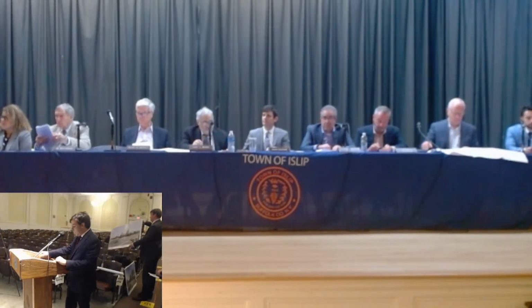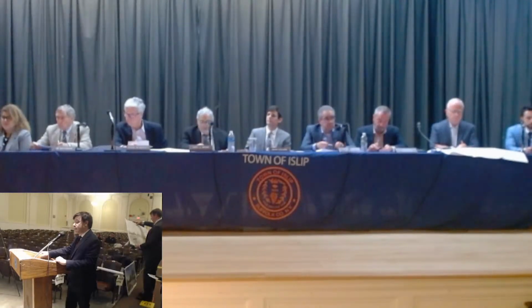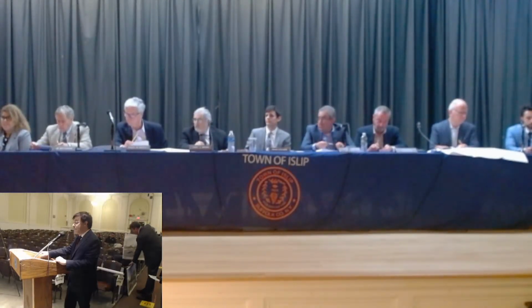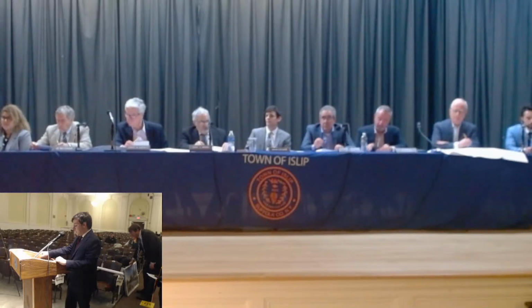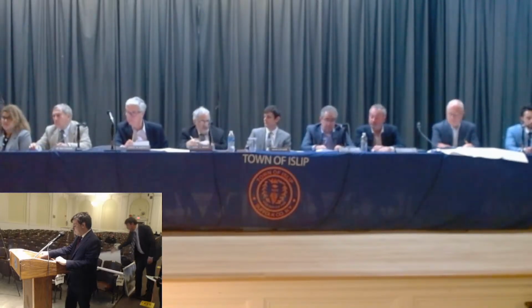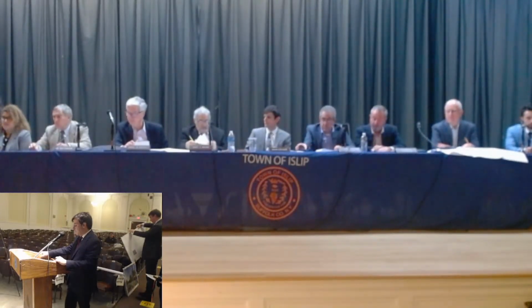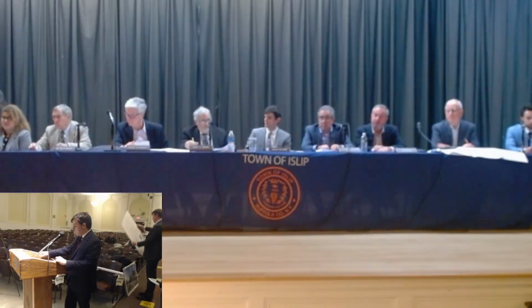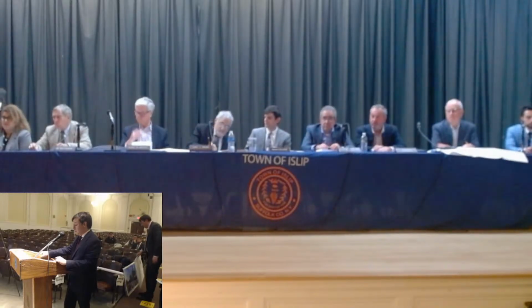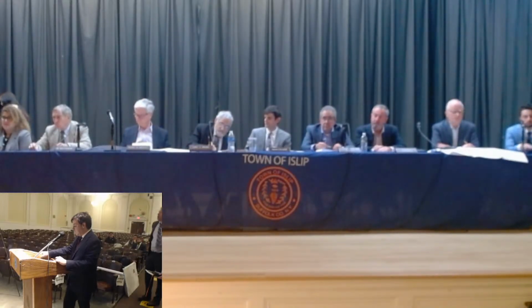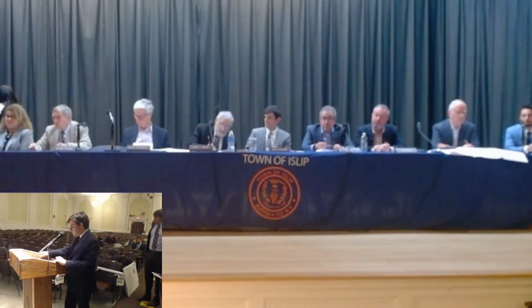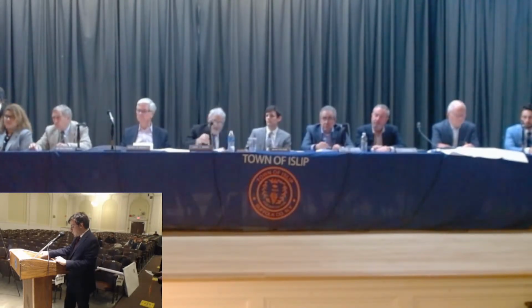As indicated in the plans filed with the application, the development of a battery energy storage facility, or BESS, will also include the development of a project substation. A utility-scale BESS connecting to LIPA's high-voltage electric grid requires a project substation with a main power transformer to increase and decrease the voltage of the energy leaving and entering the BESS. The voltage will change between the power conversion system's voltage and the voltage of LIPA's transmission system.